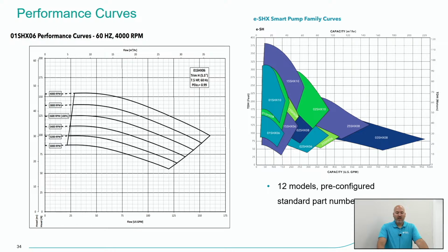With this, there are strictly 12 pre-configured models. So I know if you're looking at a normal ESH, there's plenty of different impeller trims that you can choose from, or even do custom impeller trims. With this, they're just picking a couple different max impeller trims, and you're utilizing the capability of the Hydrovar X to slow down to cover a wide range there for you. So with that said, that equated to 12 different pre-configured models that will be available to you.